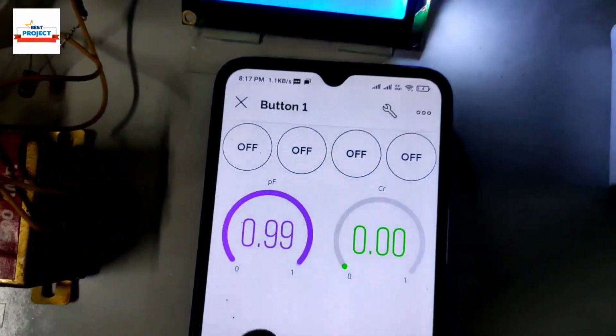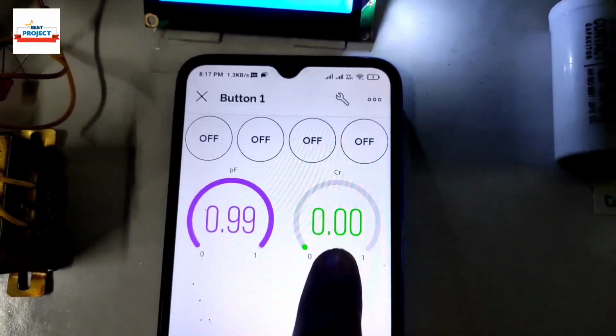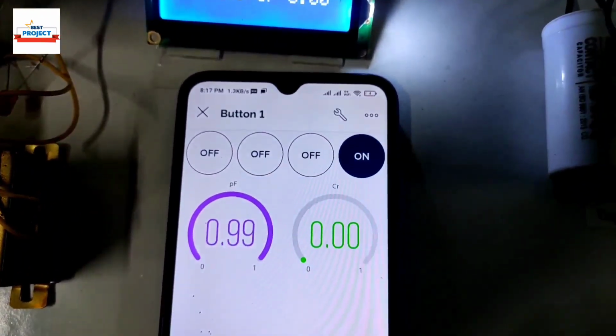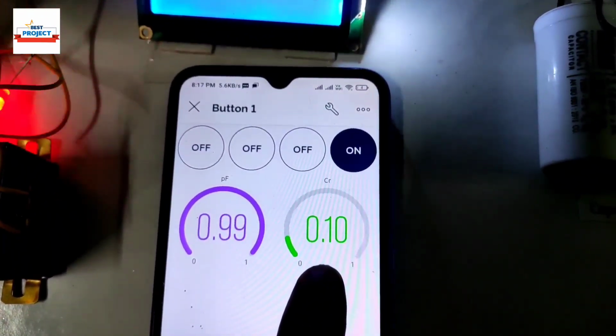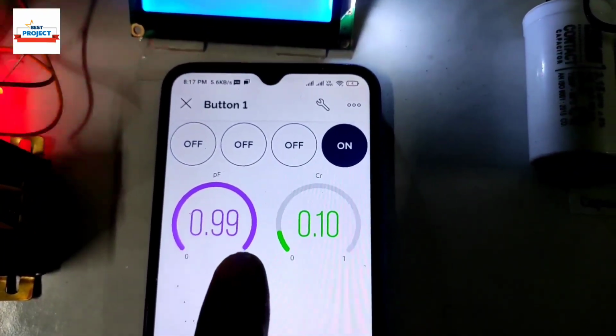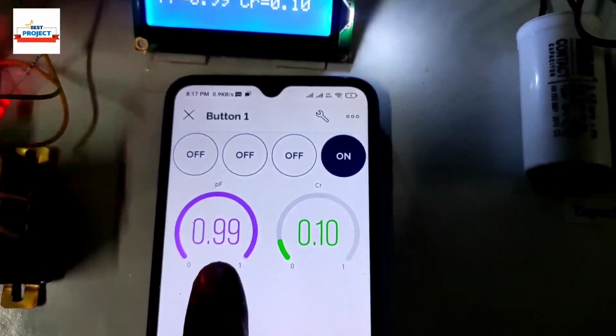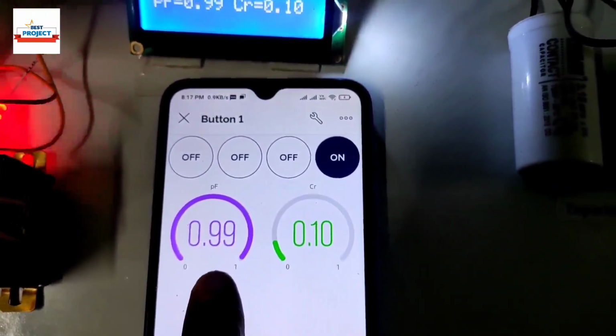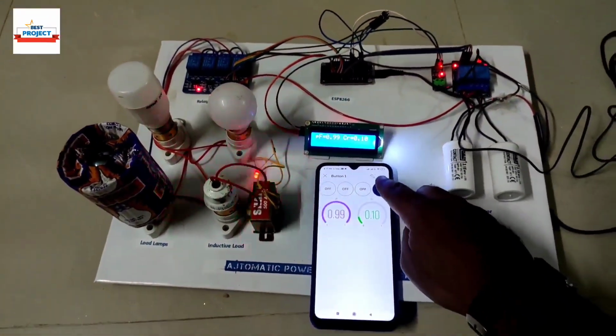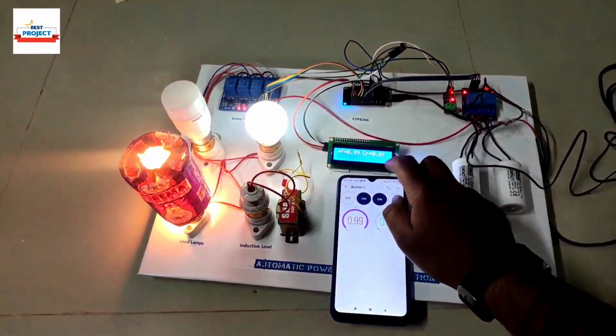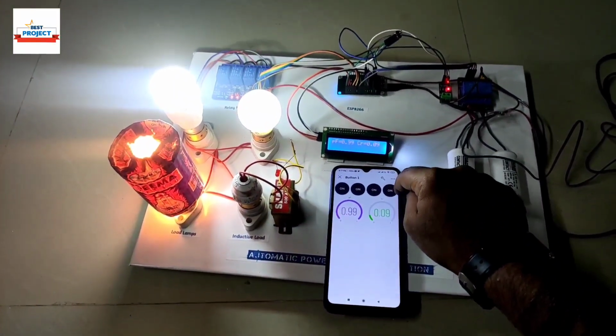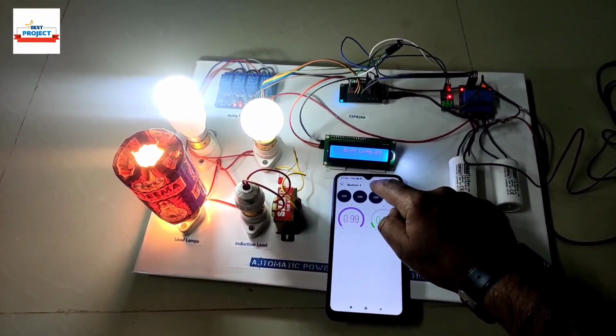See, there is no load on the line, that's why the power factor is 0.99. Okay, there is no correction, only the inductive load is there. So you can see 0.10 is in correction, okay, and the power factor was maintained at 0.99. Okay, once again turning on all the loads. Okay, turning off the loads.